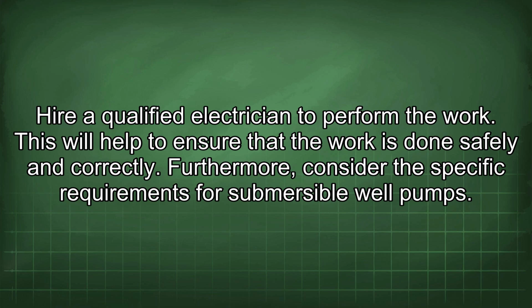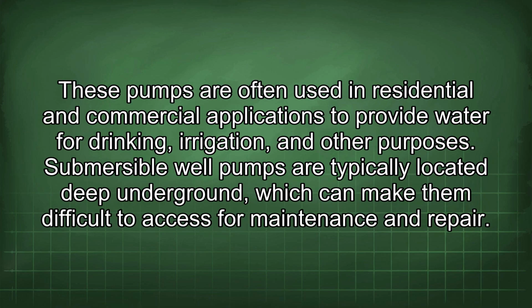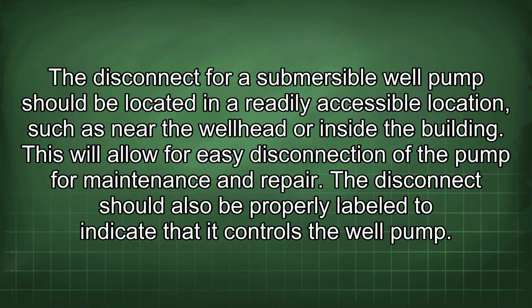Furthermore, consider the specific requirements for submersible well pumps. These pumps are often used in residential and commercial applications to provide water for drinking, irrigation, and other purposes. Submersible well pumps are typically located deep underground, which can make them difficult to access for maintenance and repair. The disconnect for a submersible well pump should be located in a readily accessible location, such as near the wellhead or inside the building. This will allow for easy disconnection of the pump for maintenance and repair. The disconnect should also be properly labeled to indicate that it controls the well pump.